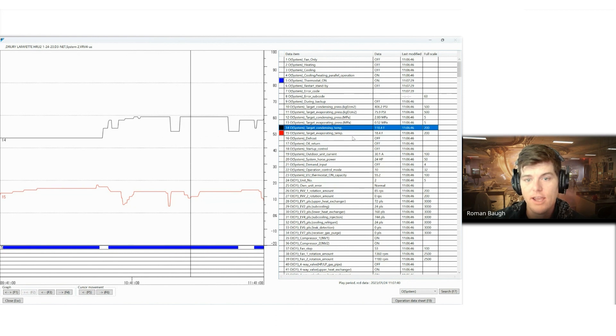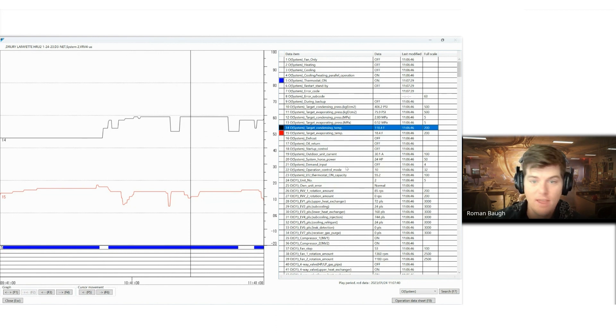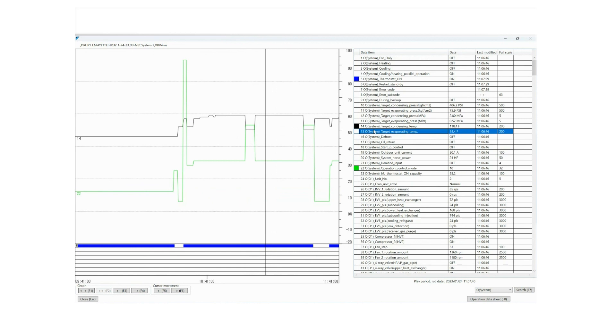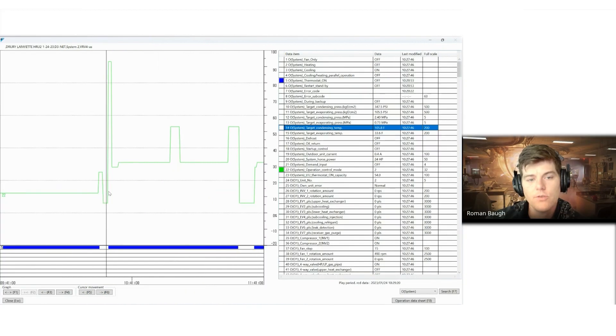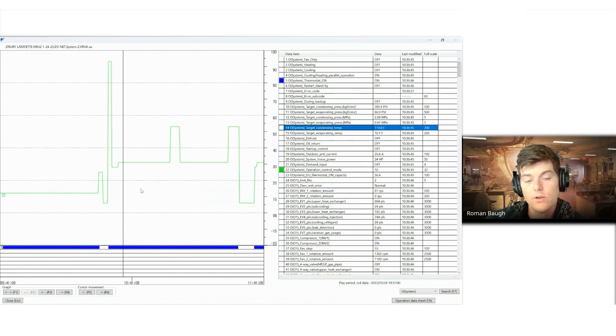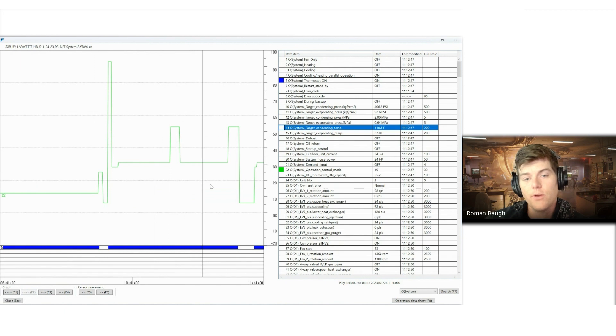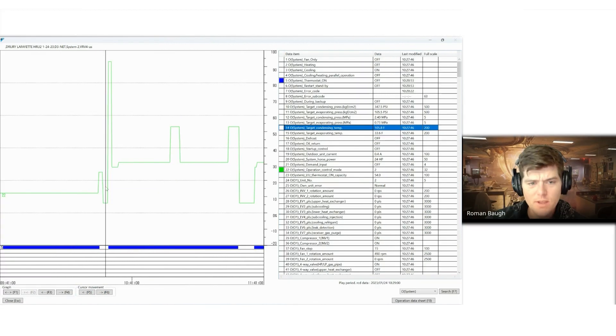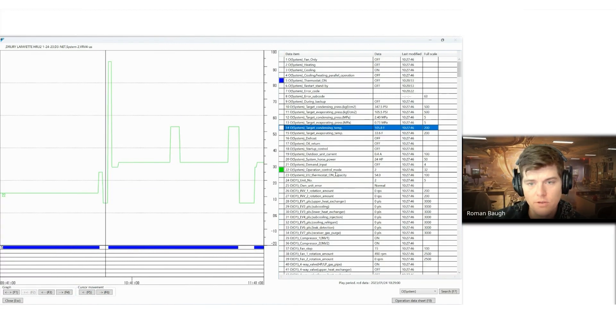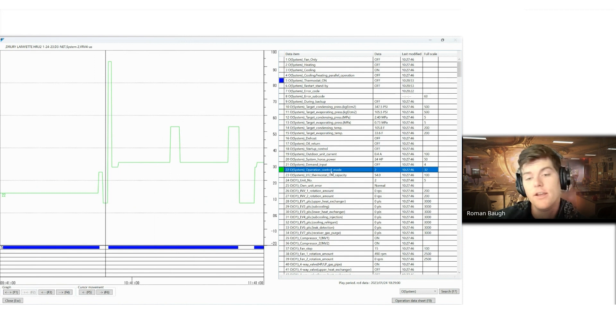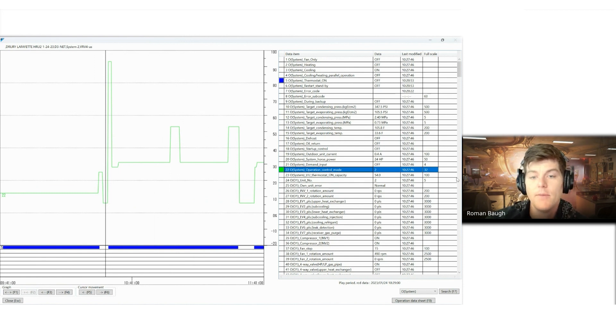That's the general explanation of it. And then last but not least, I made a video about this one, operation control mode. Operation control mode just essentially tells you what the system is doing at any given time so that you know where you should be and what looks like normal data. So this tells me as it goes to these control modes, why is it pumping itself down? Well, in this mode here, it's in residual pump down. These are things we can track now by going through the operation control modes when we're looking at service checker. But like I said, check out my other video on that, and it should be extremely helpful.